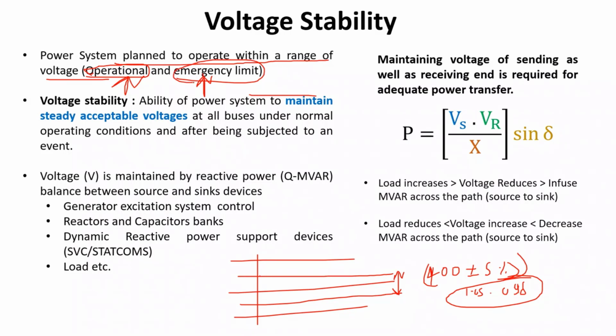The emergency limit is that beyond which you don't want to go in the system. Emergency limit is for the safety of the equipment, so you don't want to encroach into it. If it is getting encroached, there is a time-bound threshold that has been provided so that in case it reaches this emergency limit, you need to switch off the equipment. That is the limit that has been prescribed for different equipment. These voltage limits, both the operational and emergency limits, are defined in different standards in the Indian power system. So what is voltage stability?